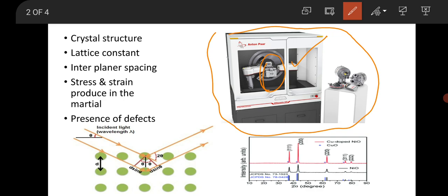This is the experimental setup or instrument for XRD. Here is the sample holder, one detector, and this is the X-ray source. X-rays come from this source — you know the basic construction: an electron gun produces electrons that hit a heavy metal target, causing X-ray emission. This X-ray is incident on the material, and after reflection, the intensity is detected by the detector. Depending upon the condition for constructive interference, you get a peak in the X-ray pattern.